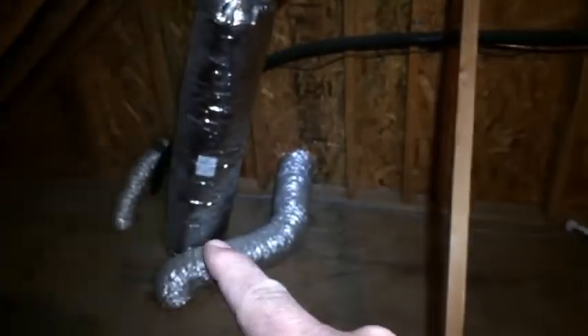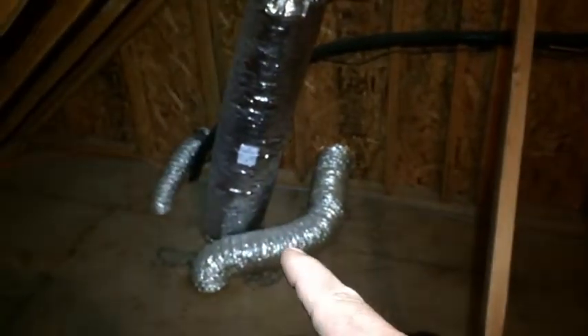But this one right here comes off as a dump zone and goes over here, and we track this down to the closet next to the restroom. So there's a closet, a restroom, then over here is a bedroom. That's one of the runs that's in the bedroom, so you can sort of see where it ended up - just to dump a little bit of that extra bypass air, I guess, to get it out of going right back through the system again and overcooling that coil. So not a bad idea.